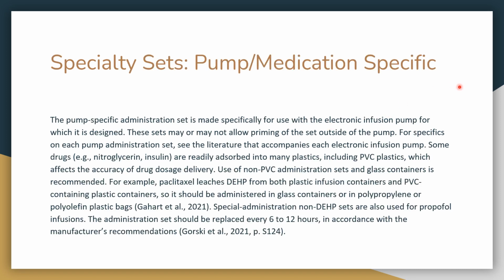So specialty sets, pump medication specific. The pump-specific administration sets are made specifically for use with electronic infusion pumps, which is designed. These sets may or may not allow priming of the set outside of the pump. So basically, if you use a specific pump, there may be a specific tubing that can only be used with that pump due to the pump's makeup, meaning it may have a certain slide clamp that has to be used, so it's specific to that pump. These are usually non-DEHP sets, and they still should be replaced every 6 to 12 hours, or in accordance with your manufacturer's recommendation and your policy as well.